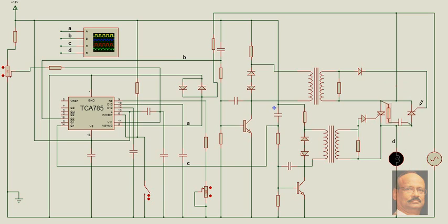Here is a circuit where we have back-to-back SCRs. There is one SCR here, and another SCR here. This of course is a snubber network, an RC, which is usually connected across the thyristor. And these SCRs can be of very high power, it doesn't matter, it could be 50 amperes, 100 amperes, 200, 500, 1000 amperes also, as long as the pulse transformers, these two pulse transformers, are driving the gates.